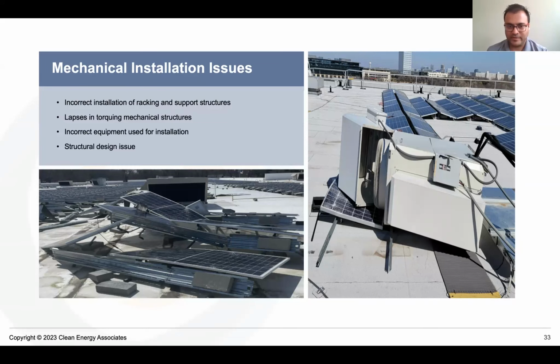A year and a half later, we got a call that there was a wind event. Apparently one of the modules flew up from the roof and landed right on a crosswalk, a foot from a lady walking there, she was very lucky it didn't land on her. Another issue is that ballast blocks on the roof are sometimes taken off by people and used to hold down other things on the roof. That's a no-no, because that's an engineered ballast block with weight based on wind load.